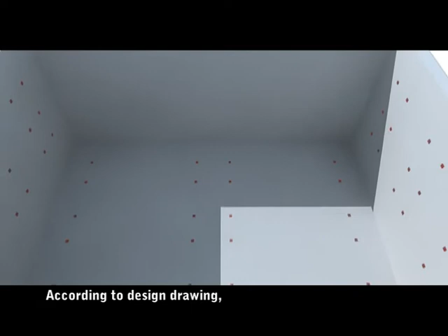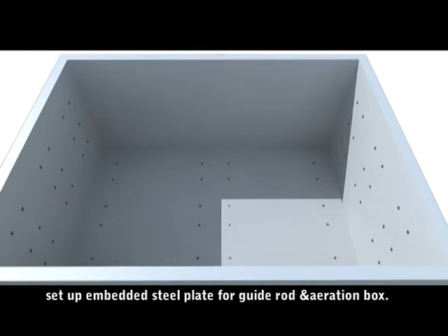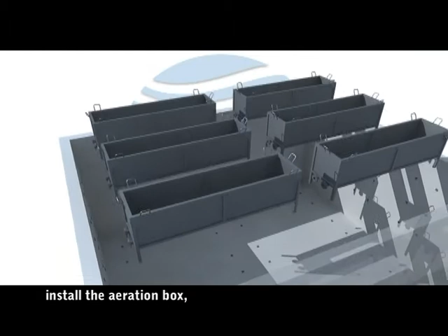1. Installation of membrane module. According to design drawing, set up embedded steel plate for guide rod and aeration box. Clean the MBR tank, install the aeration box. At the same time, fasten it and level it. Leveling error control is about 5 mm.